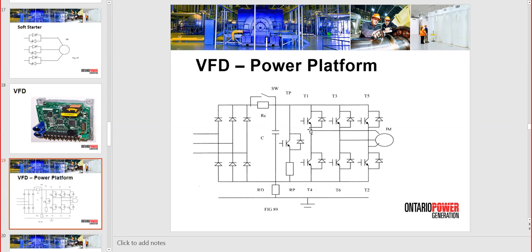What we observe here, the inverter is a 4-quadrant operation. It actually can absorb voltage and current in one direction, but can reverse the direction of current charging the capacitor, and also can reverse the voltage on the motor by going forward and reverse. So the inverter covers all 4 quadrants, positive and negative for voltage and current, but the diodes are 1 quadrant only. So that's the discrepancy in an off-the-shelf inverter VFD, because they are not even. So that's why we have other types of VFDs, as we're gonna see.